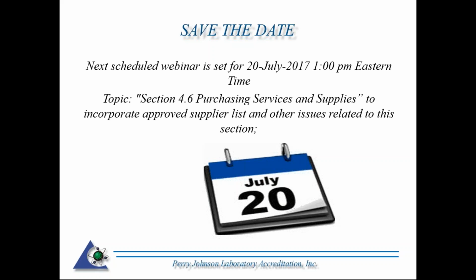I realize, particularly from being on the side of the calibration lab, that most often the customer does not know what method is to be used, and they're relying on the laboratory as the expert to determine that. However, if it's not specified during the request, keep a record of it when you as the laboratory offer the tender back to your client.